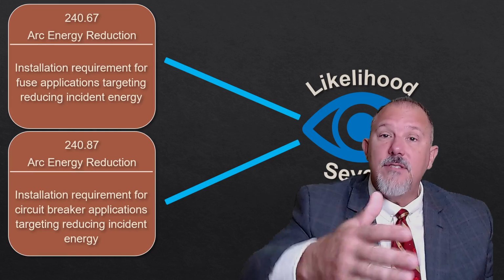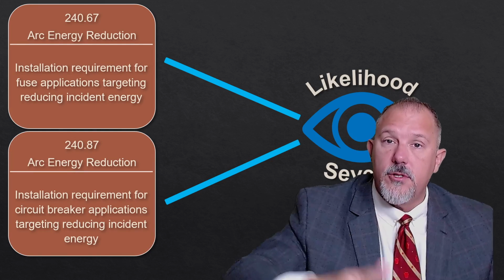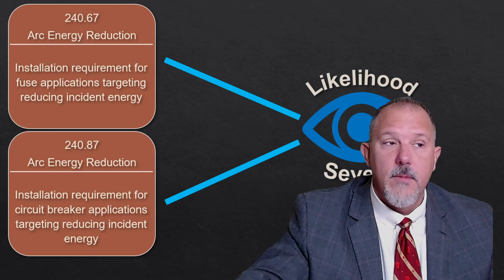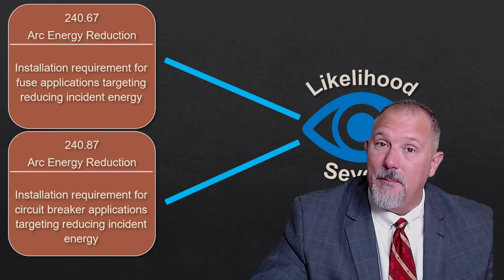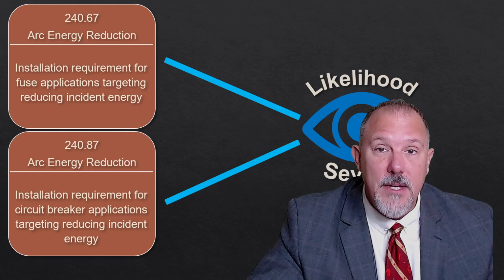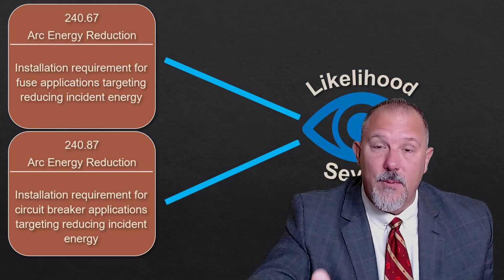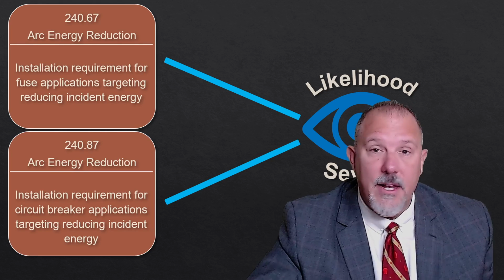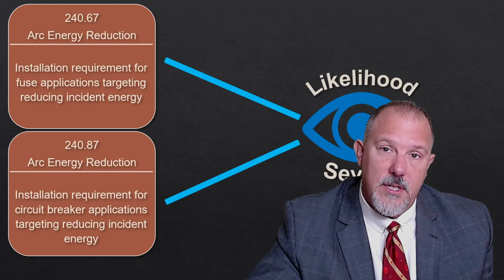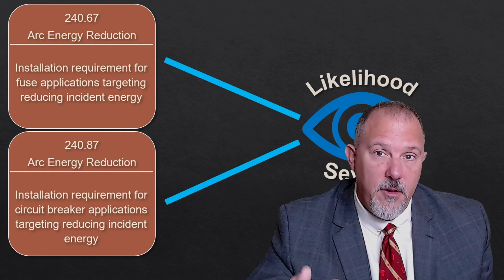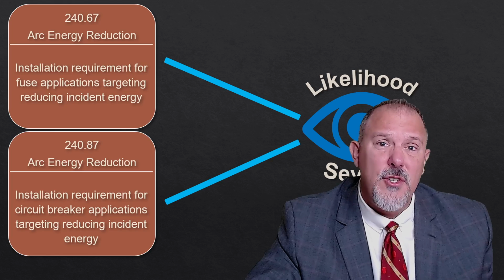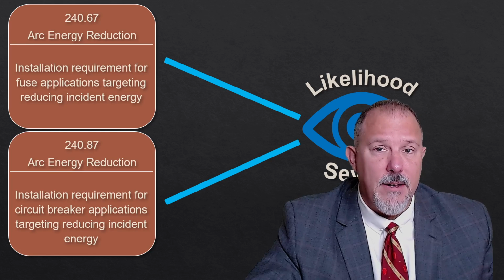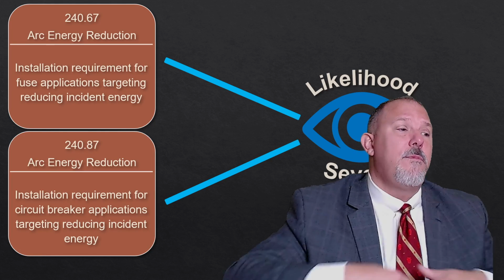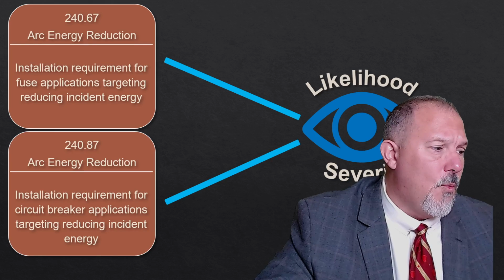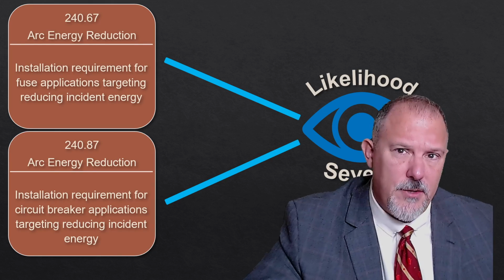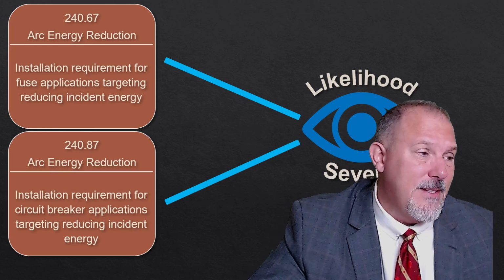This is outside of ground fault protection of equipment, which also sought the same goal, but I would argue is not doing as good of a job, because with a 1 second clearing time, your energy can be very high. And with the fact that a ground fault in those systems will go to a 3-phase fault within 2 cycles, I don't know that GFPE delivered on what it wanted to do. But remember, it was the only technology in 1971.